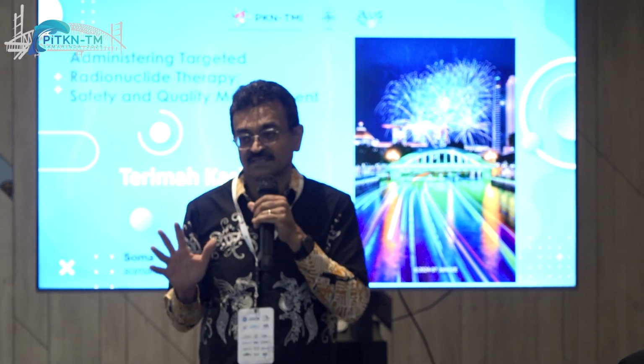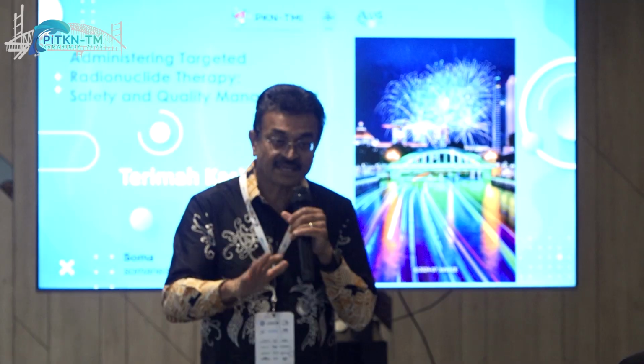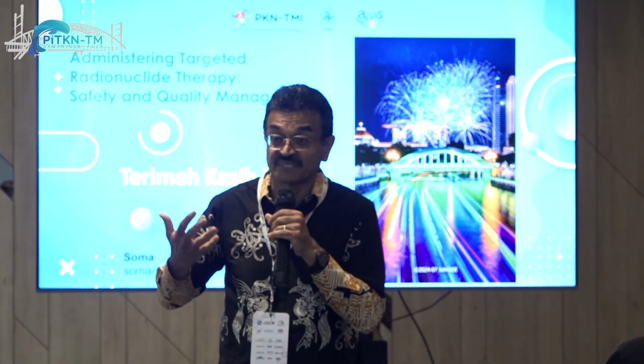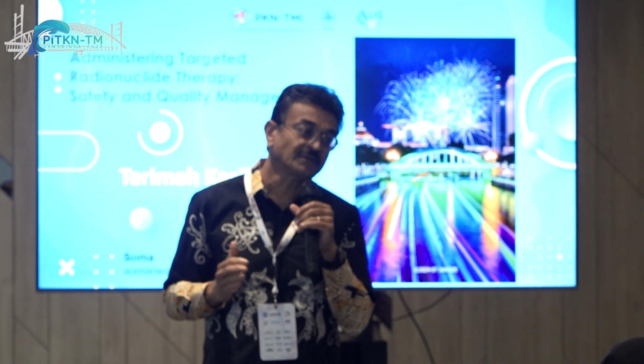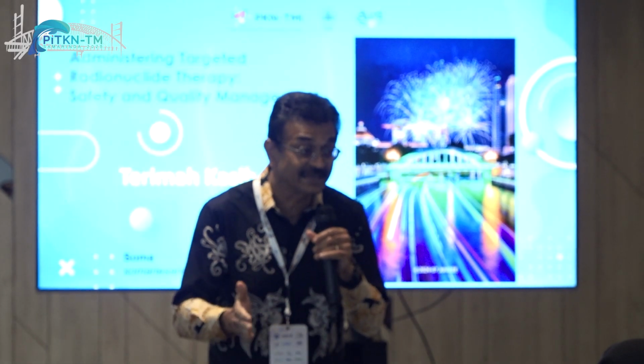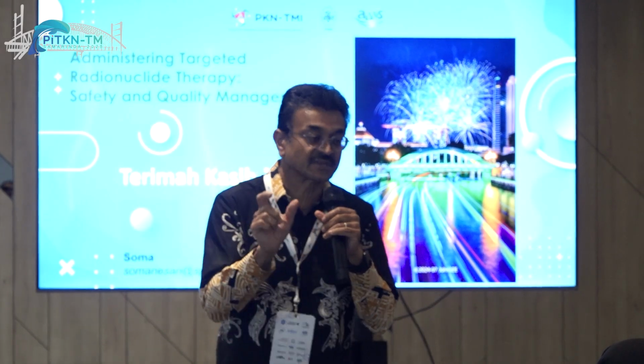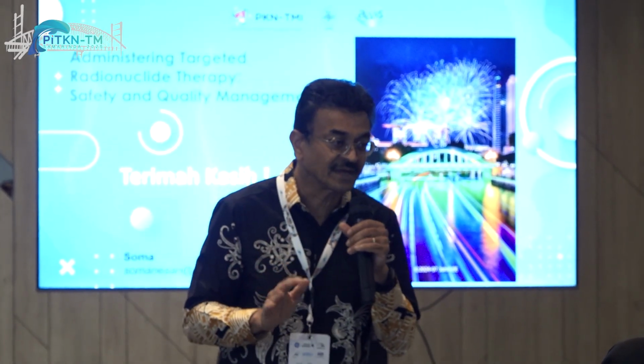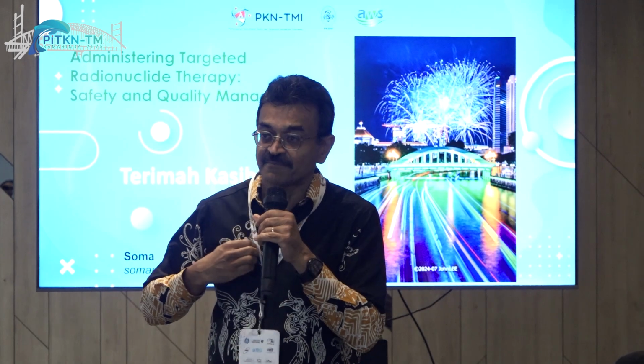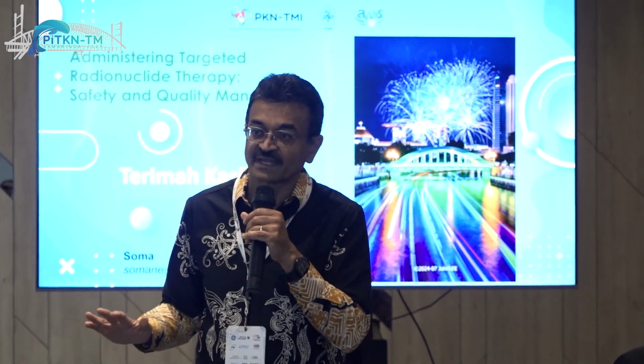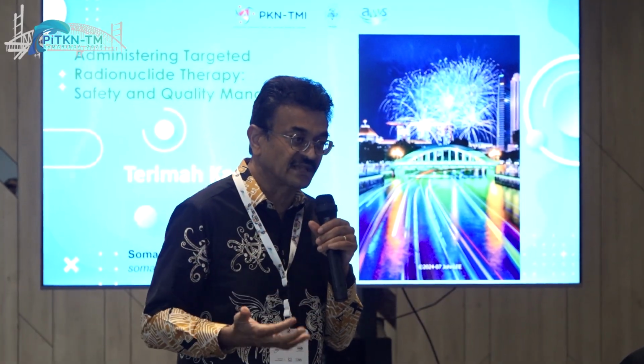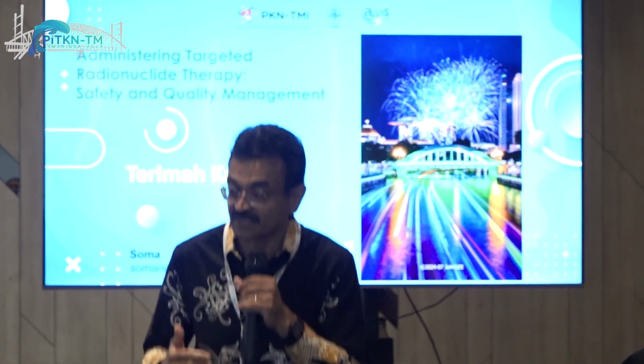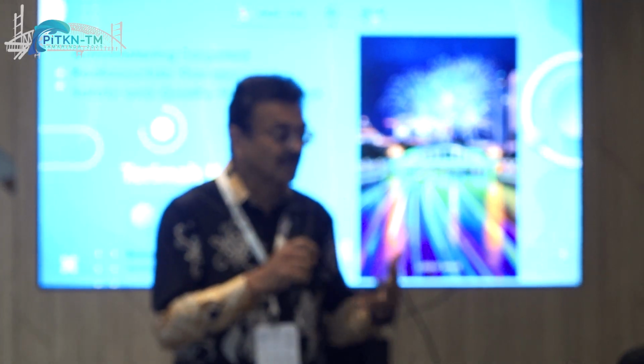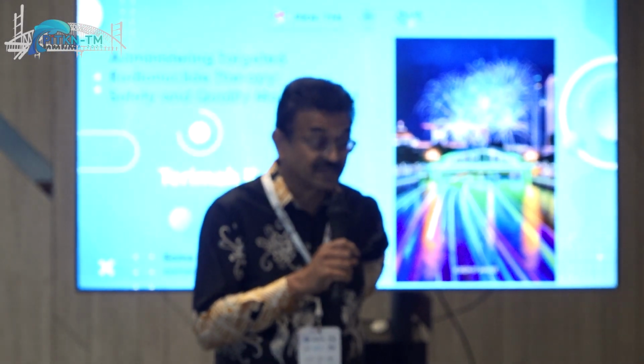A lead apron is useless when it comes to F-18 FDG, but yes, it has given the nurses a sense of safety, but it's a wrong sense of safety, right? Because when you are dealing with 511, the half-value layer of fluorine-18 for lead is about 13 millimeters, and it won't work, because our lead apron is about 0.25 to 0.5 millimeters. It won't work at all. In fact, you'll be inconveniencing yourself and your staff if you make them wear a lead apron, because you're going to stand up, sit down, and get backache for 8 hours of the day. So therefore, use a shield when you're doing 511.